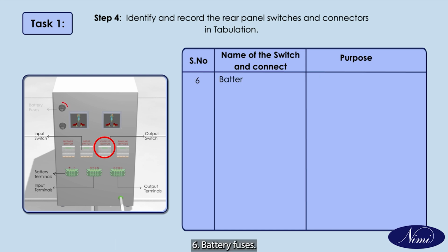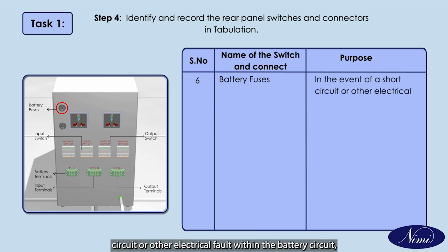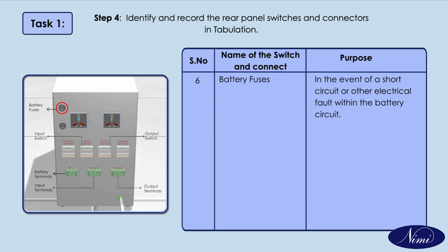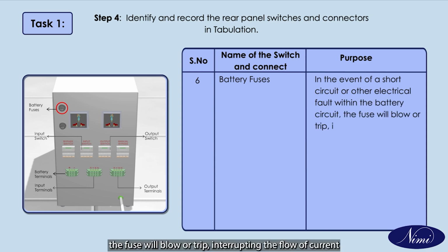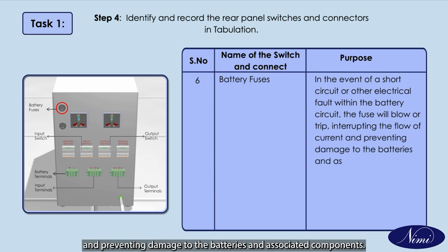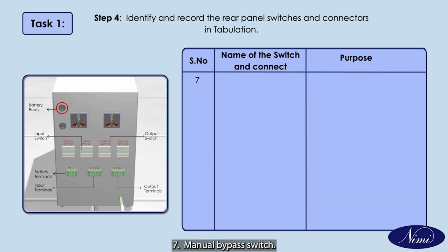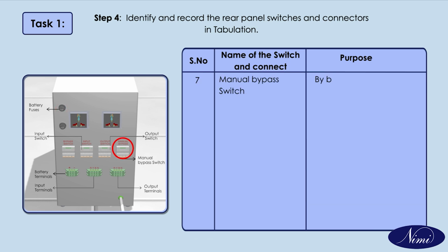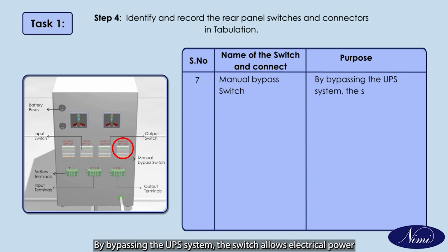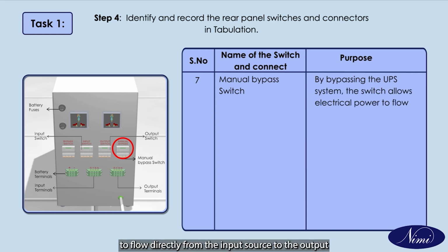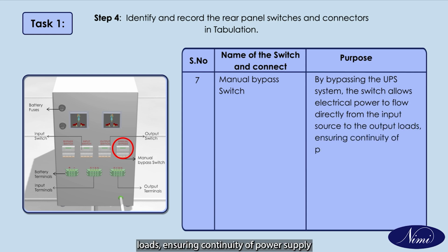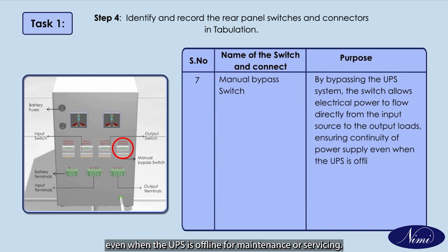Number 6. Battery fuses. In the event of a short circuit or other electrical fault within the battery circuit, the fuse will blow or trip, interrupting the flow of current and preventing damage to the batteries and associated components. Number 7. Manual bypass switch. By bypassing the UPS system, the switch allows electrical power to flow directly from the input source to the output loads, ensuring continuity of power supply even when the UPS is offline for maintenance or servicing.